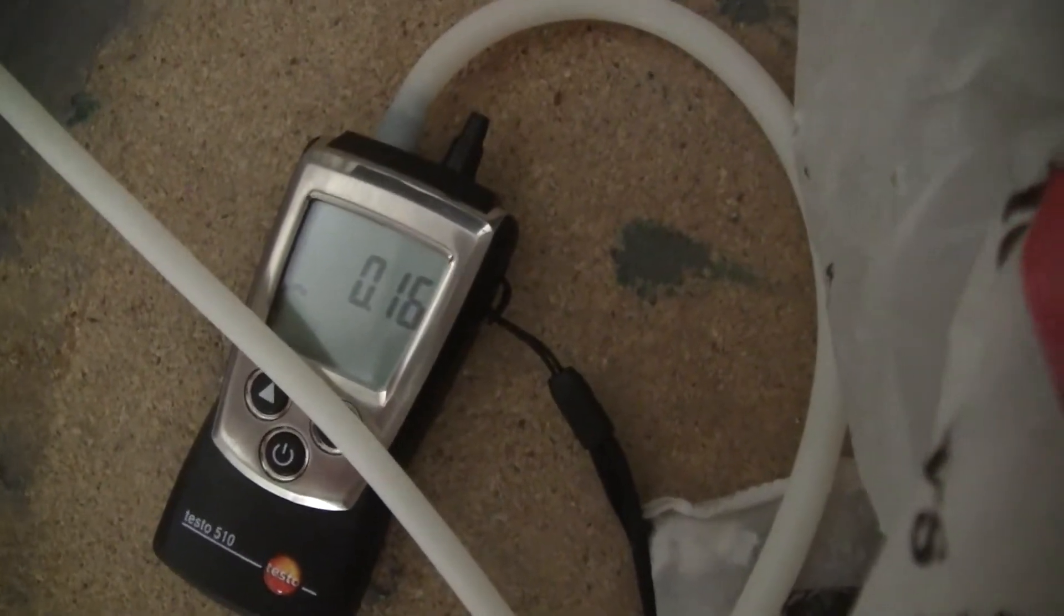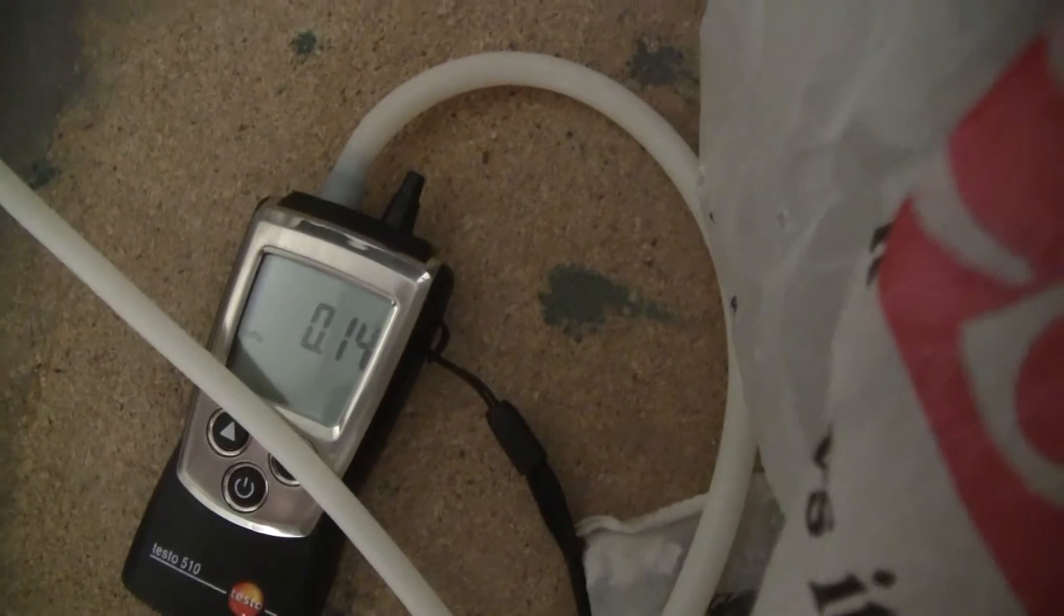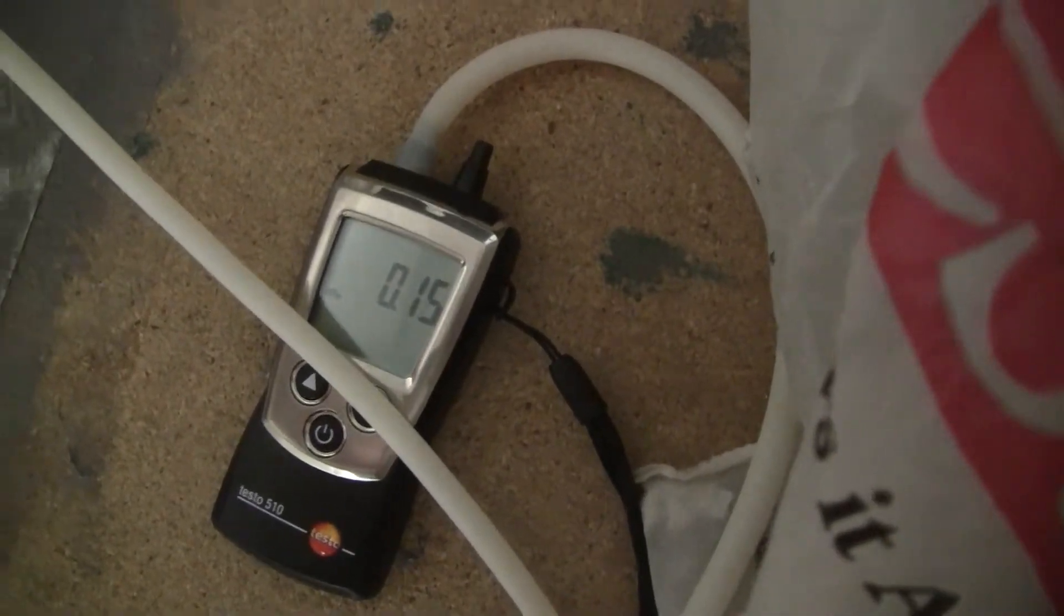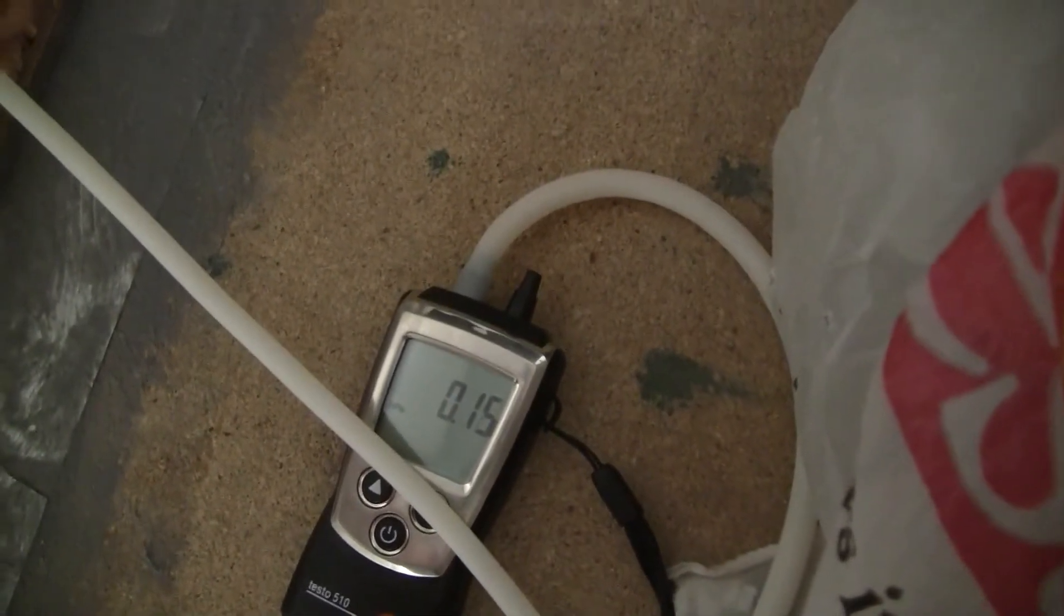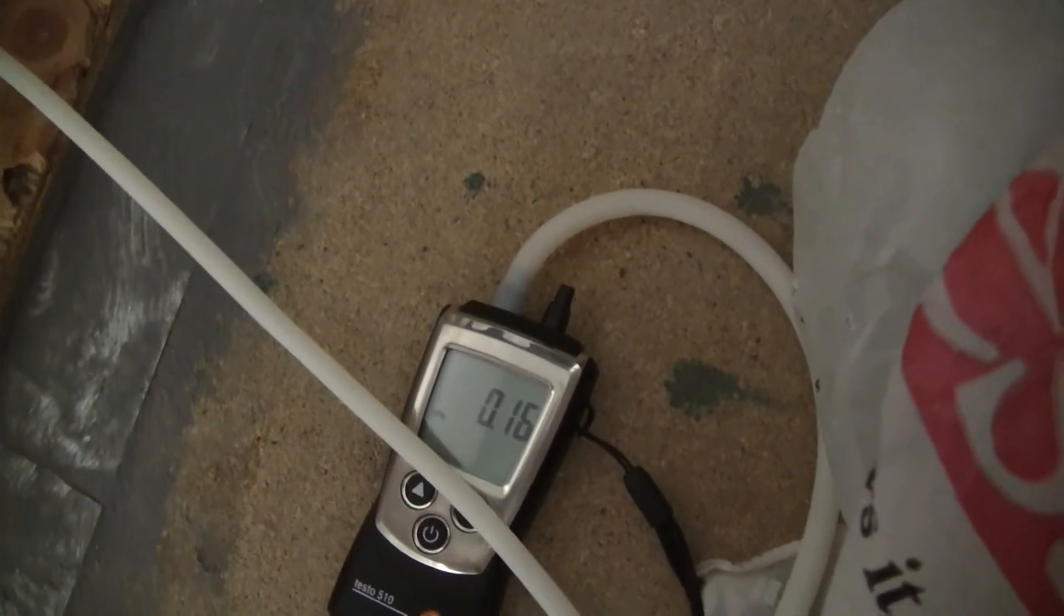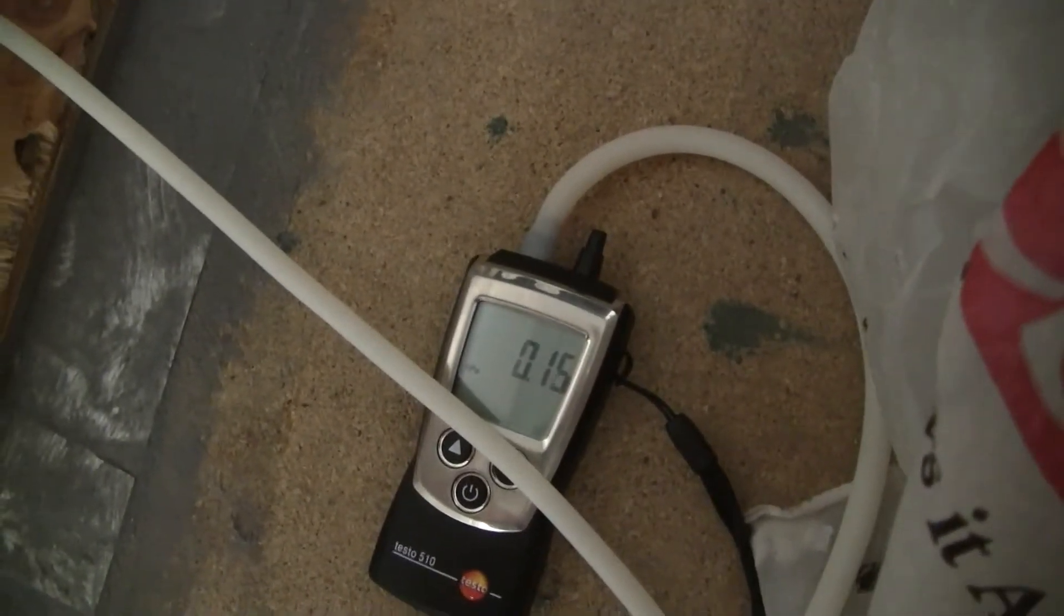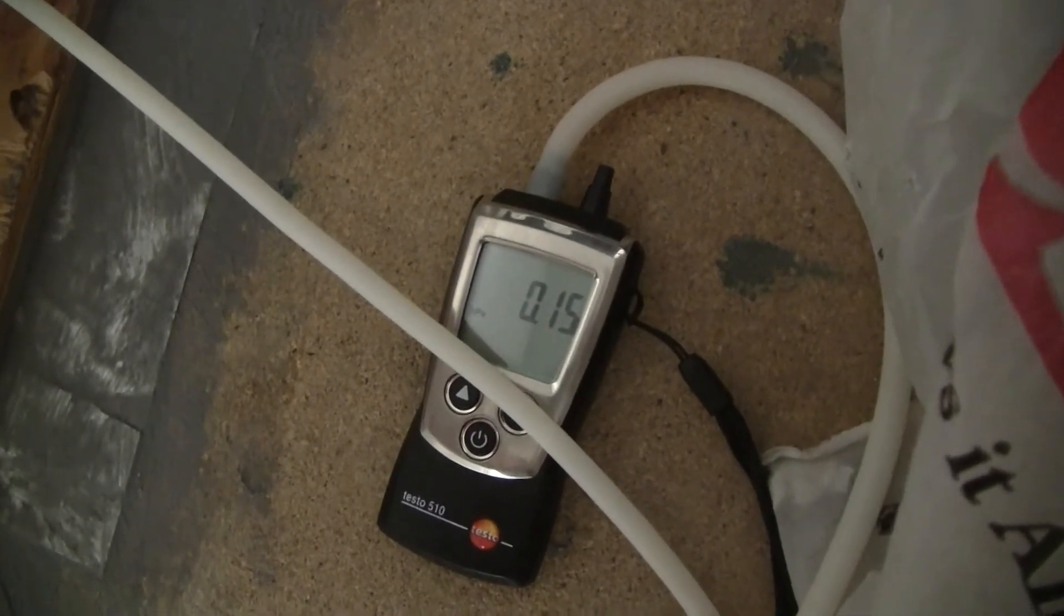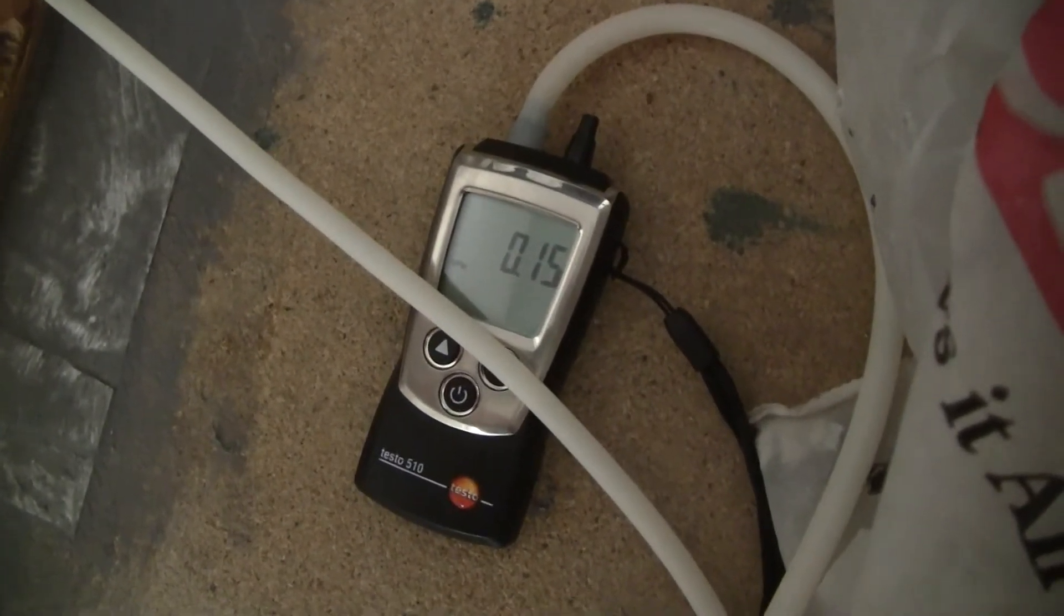That one that was like 23, 24, this is on the same plenum. Anyway, I'll put all this information in a video as soon as I find my notebook and I can compare them. It would be interesting to know when fixing them if the pressure should rise. It should absolutely.